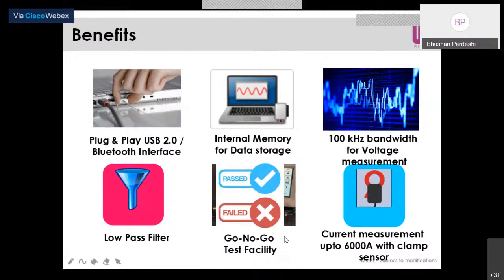What is the go/no-go test facility? One can set a band range for voltage, mostly used in testing industries where devices need to be tested. You specify a higher range and lower range, and if a reading falls within that range, it gives a buzzer sound, meaning the object is okay and can proceed. If the buzzer doesn't sound, the device has an issue and should be set aside. This helps in the testing process across industries, which is why we've given this go/no-go feature.